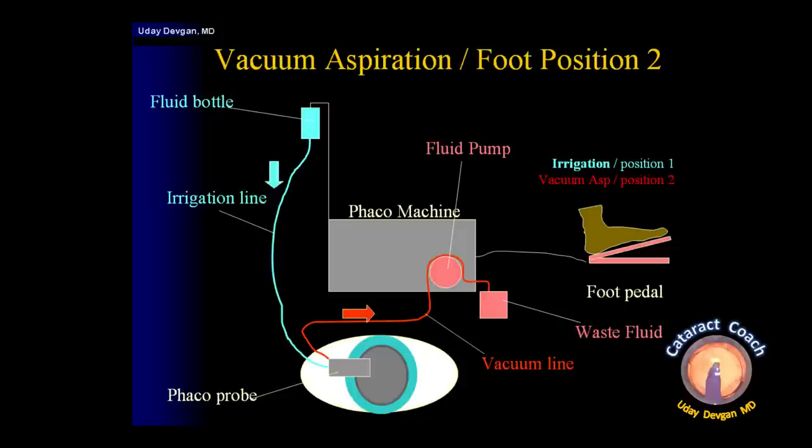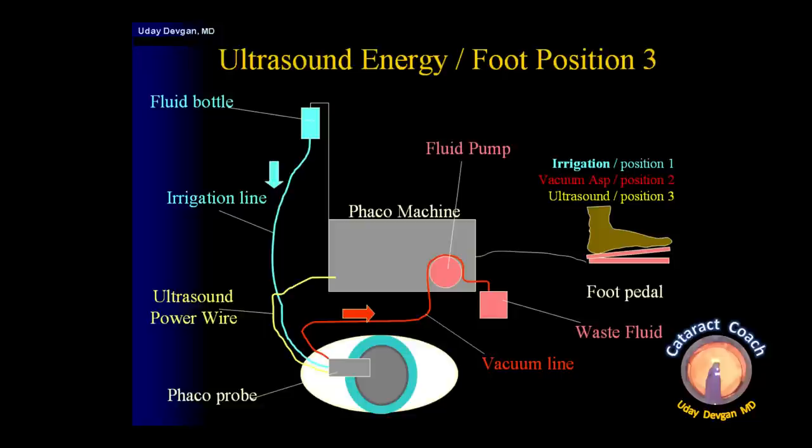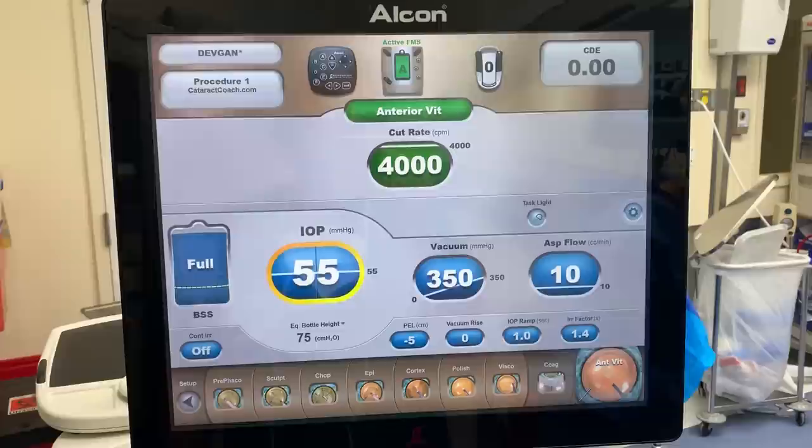Foot pedal position two is for vacuum aspiration — the vacuum level is also related to flow. We'll discuss the different pump types, peristaltic versus venturi, but position two controls how much vacuum we want inside the eye. Position three, with the pedal all the way down, delivers ultrasonic energy to break up the cataract. The different types of phaco power modulations — pulse mode, burst mode, and combinations — will be covered in upcoming modules.